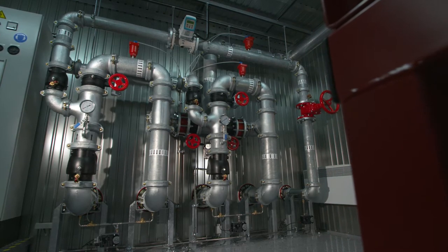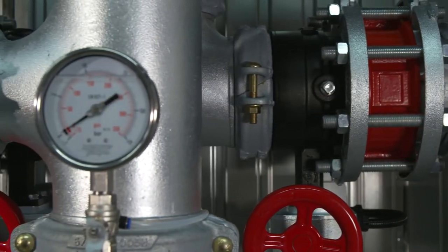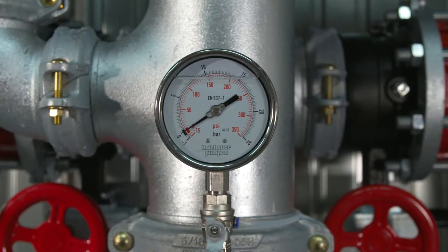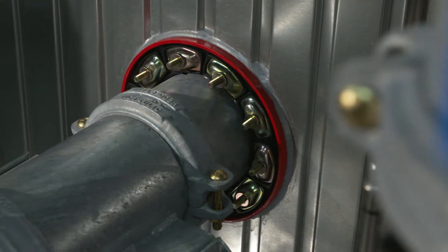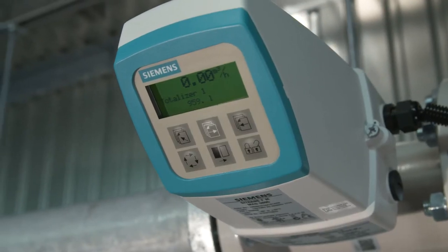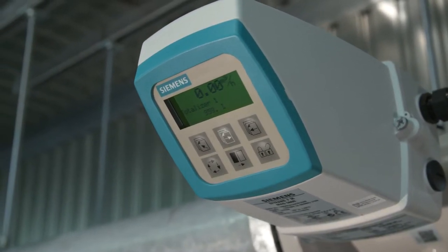On the pressure side, the external submersible pumps are piped from the outside into the fire pump station with all the necessary fittings for easy on-site operation. All pipe penetrations are driving-rain proof. A test pipe with a VDS-approved magnetic inductive flow meter is available to verify pump performance.